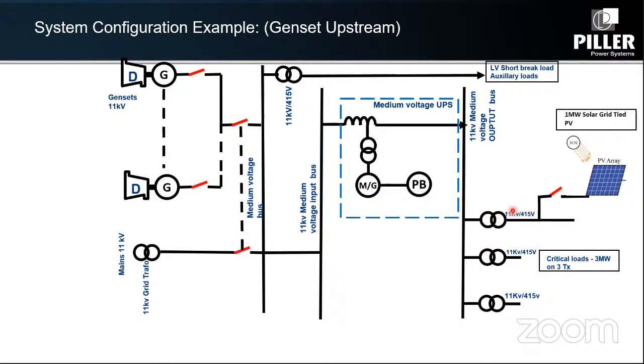So here the customer has a 3 megawatt load connected on these 3 step-down transformers, but wants to use photovoltaic, say 1 megawatt. With the technology we offer, during the daytime that 1 megawatt could be fed directly after the step-down transformer, reducing grid consumption by 1 megawatt. The UPS would have current sensing at this point. We'd be able to feed 2 megawatts from the grid for the load, and the 1 megawatt could be used directly from the solar photovoltaic, reducing energy consumption.